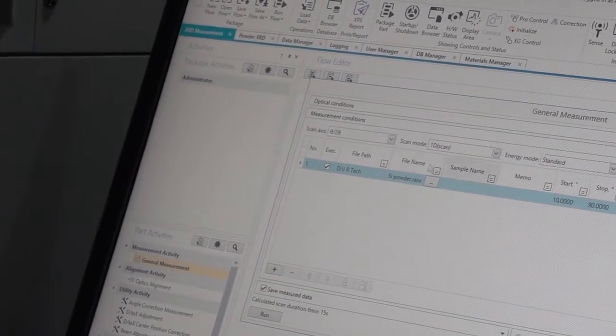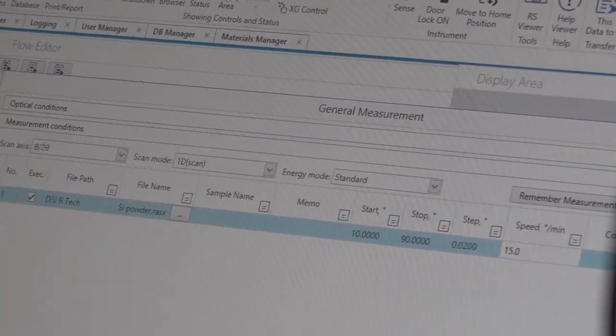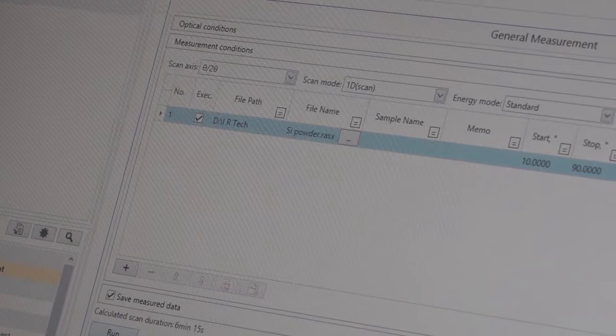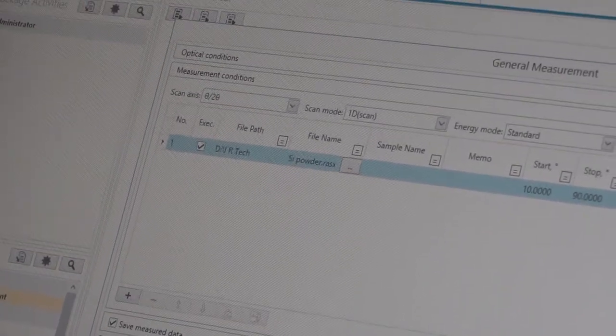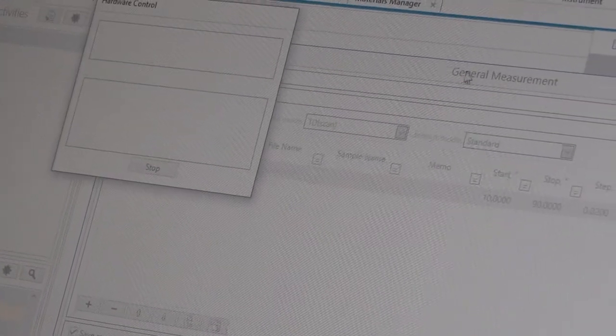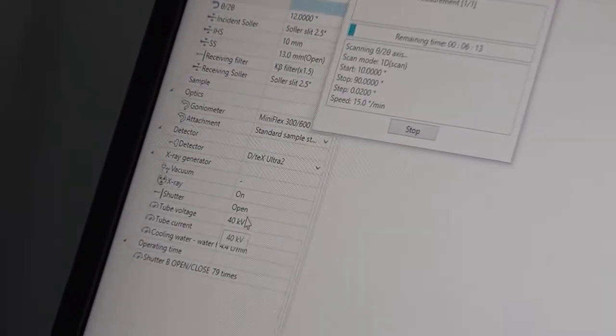Okay. So this will be default only, scan mode is a 1D scan. The scan axis is theta two theta. Everything will be the same only. To run this, see, the run command is here. You can run it. And now the shutter is open. It is showing here. See, shutter open.